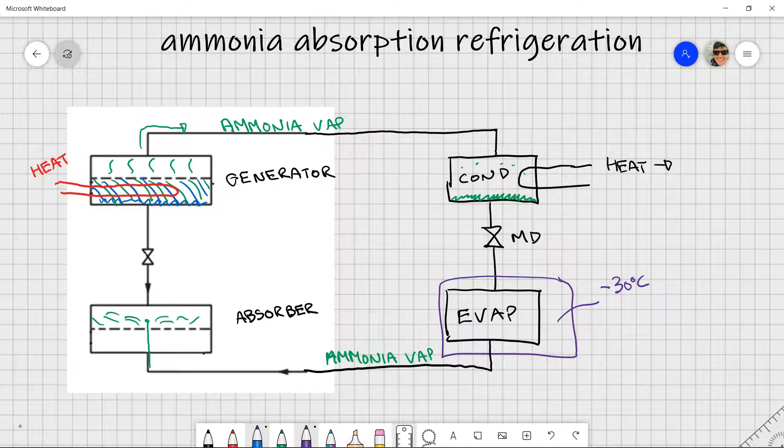So the ammonia that leaves the evaporator is going to come up, and I'm going to allow it to exit out and sort of make its way into this upper cavity. This vessel is known as the absorber. And we can imagine by the name what its function is. Its function is to absorb that ammonia into something, and what that something is is going to be water. Here's where we get the water from. When we drive off the ammonia out of the generator, what's left is mostly water. So we recycle that water downwards and put it into the absorber.